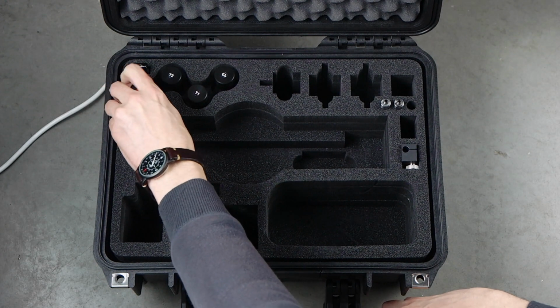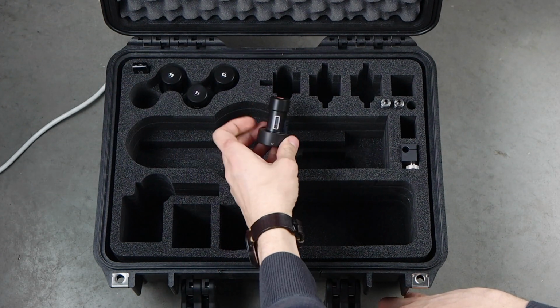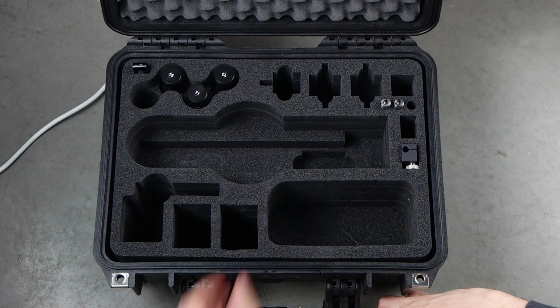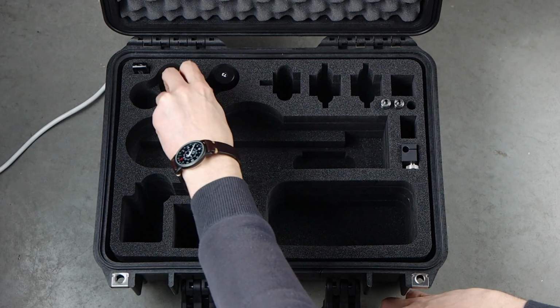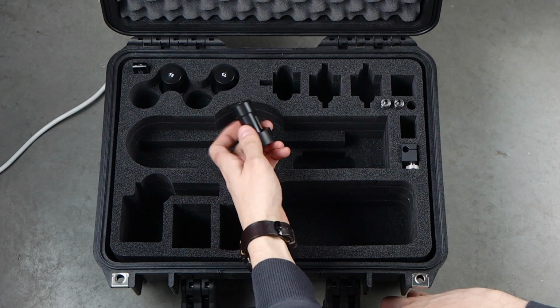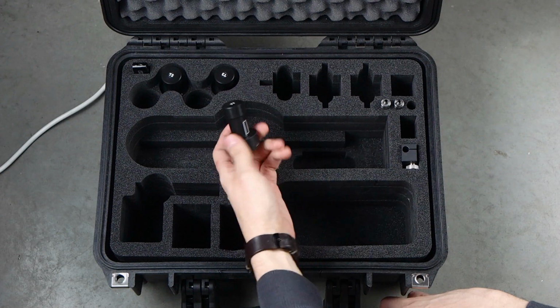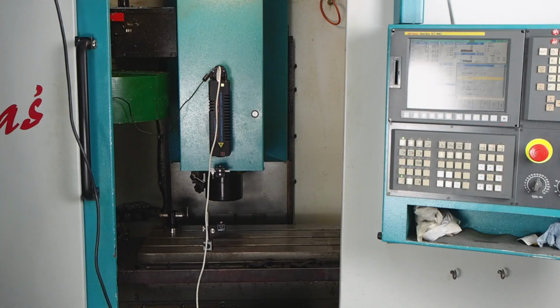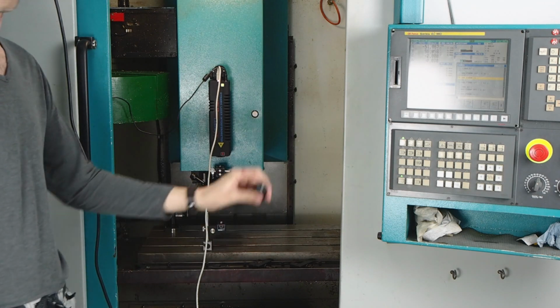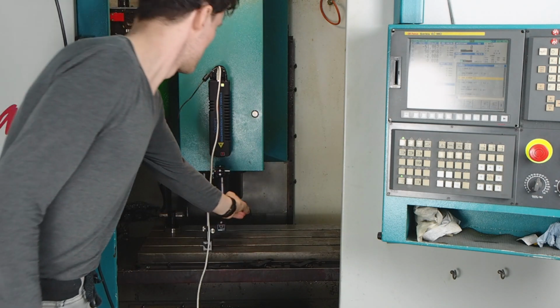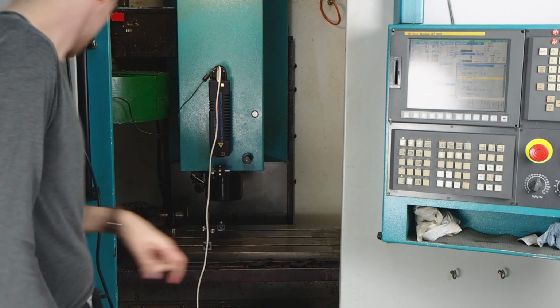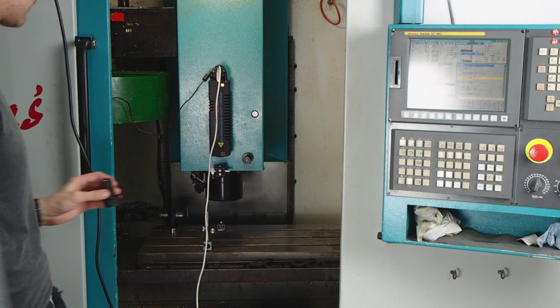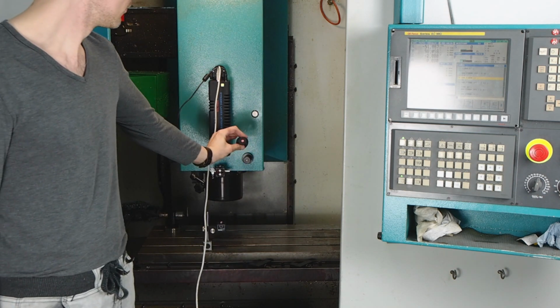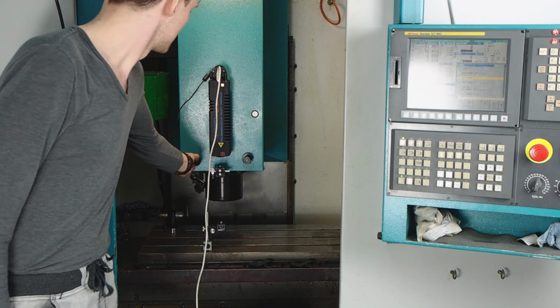Take the atmosphere sensor and the temperature sensor. One temperature sensor is enough for this small machine, but if you are measuring a larger one, you should consider placing them to get a good temperature gradient. Temperature sensors should be placed along the measured axle. The atmosphere sensor should be placed as close to the laser beam as possible.